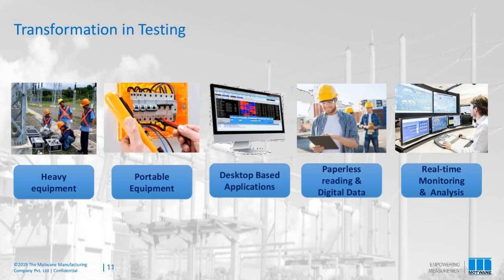This application could have information on the asset you're testing, who you're testing it for—whether it's a utility, industrial customer, or commercial space—and a record of the previous result and the time before that. So the test engineer isn't just doing data entry and analyzing results 15 or 20 days later when creating the report, but is actually analyzing it at that point in time. That makes the speed to decision-making so much better.